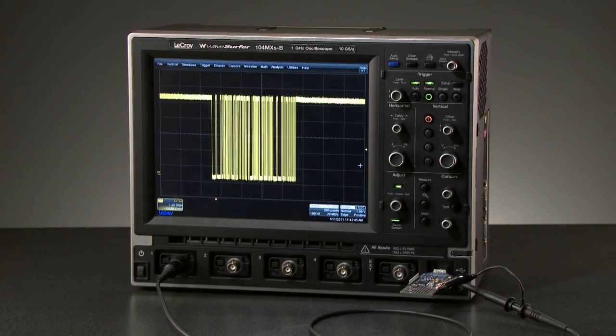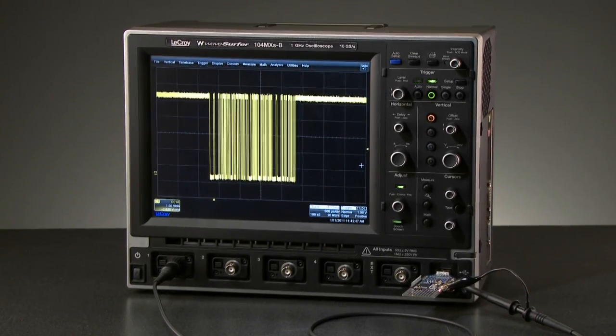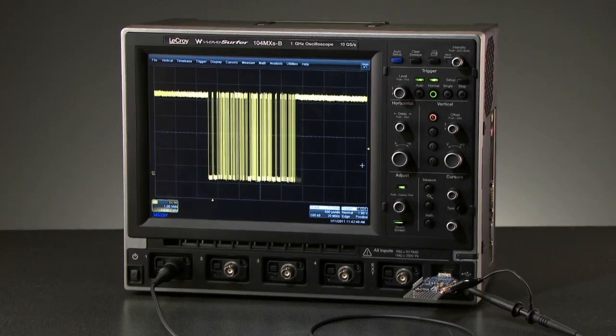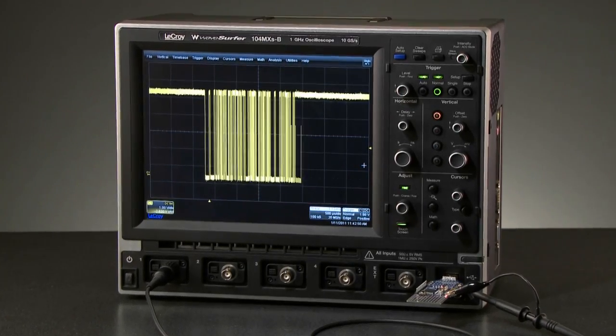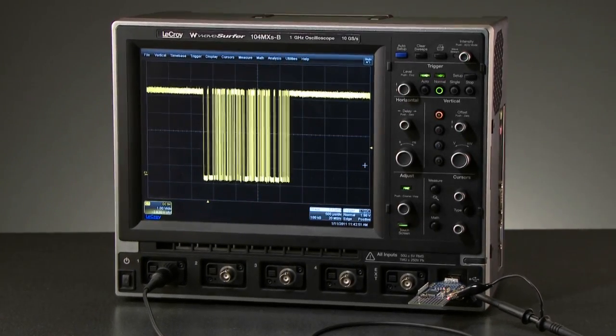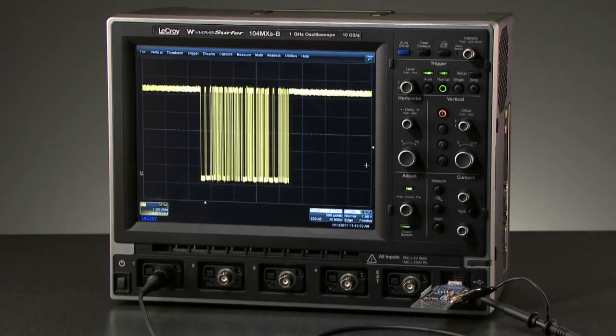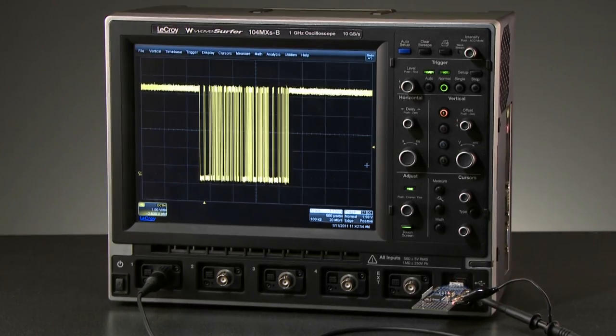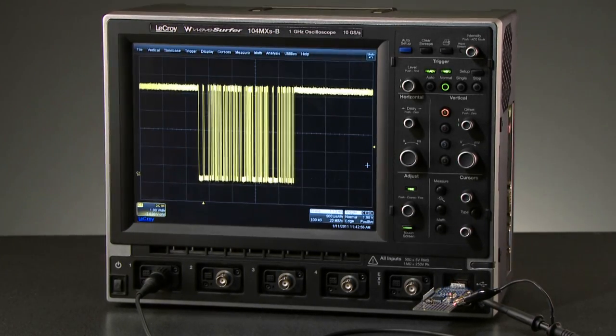Sequence mode is a powerful acquisition mode, standard in the WaveSurfer MXs-B and MSO MXs-B oscilloscopes, that segments the memory to maintain high sample rate and enable fast triggering.